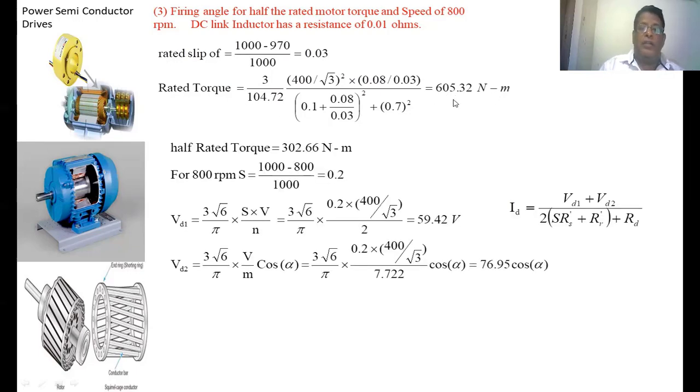Now we want half the rated torque, which is 605.32/2 = 302.66 N-m. The speed of the induction motor at half-rated torque is given as 800 rpm. The slip corresponding to that speed: S = (Ns - N)/Ns = 0.2. Vd1 = (3√6/π)·(S·V/n). Substituting all values, we get 59.42V.